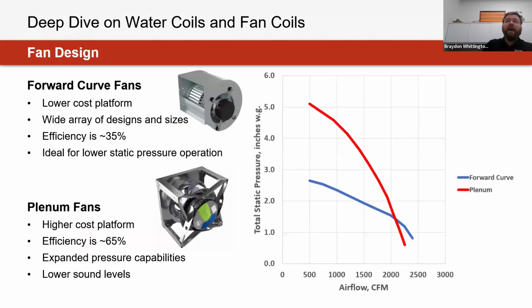In terms of fans that are commonly paired with these products, the most common one that you're going to see is the forward curve fan. It's a pretty effective solution, I would say, for low static applications. What I mean by that, when talking about this equipment, is that normally you're going to see these at up to 2 inches of static or below that, especially when dealing with fan coil equipment.